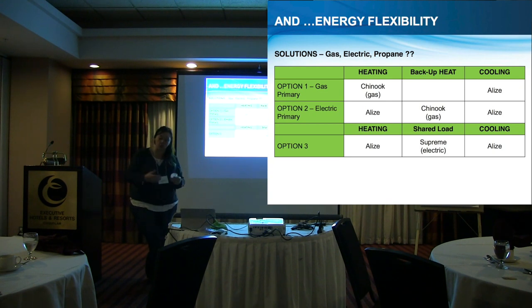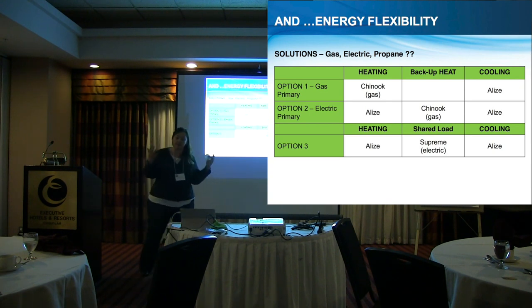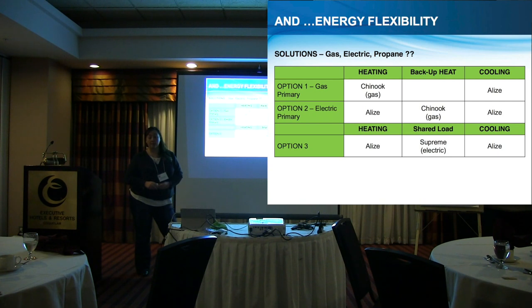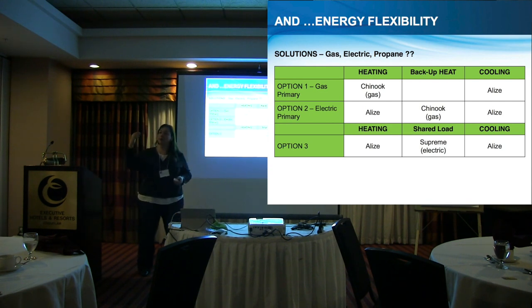We design everything to cooling. We design everything to the highest CFM potential. So sometimes you do end up with multiple rooms. Sometimes you end up with those great rooms and zero walls, right? So even in an unfinished basement, we don't have any walls to get down into. So then we'll get into downflow positioning.